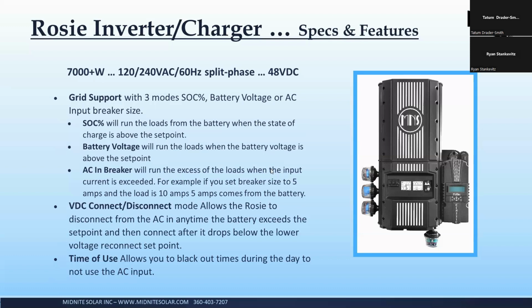VDC connect or disconnect is a little bit like grid support, but a little different. Where grid support can actually add to the grid, so if you have, say, a 2 or 4,000 watt load and you only have 1,000 watts of PV available at that moment, it can take the rest from the grid. VDC connect slash disconnect actually opens the relay, and everything is coming from the solar system at that point. So you could have that set for, and a good example is my system in Florida. I don't have a net metering agreement, so it runs my air conditioning and everything.